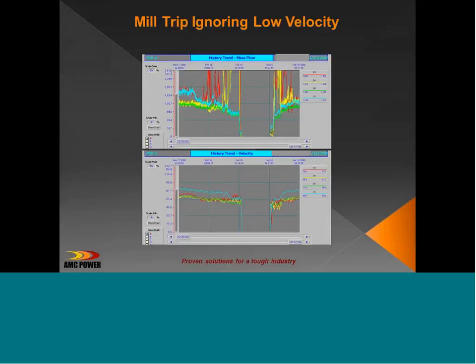And in this case, we can see that this mill actually tripped. There was no purge in the lines, and any coal that was moving through the coal pipe settled out. We combined that with the slug of coal that was delivered, and there just was too much coal in pipe 32R, and it caused a fire. We've seen this at many utilities, going back in data, and we never want to see it. We hope that our equipment is being used to prevent fires. And here's how we can do that.